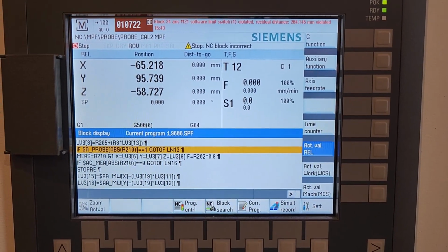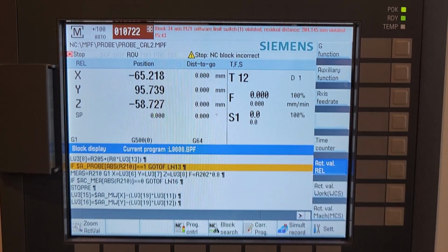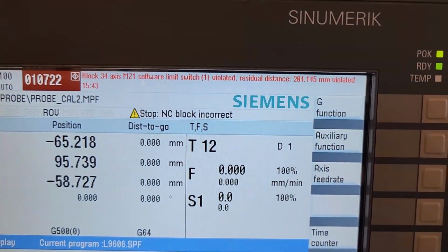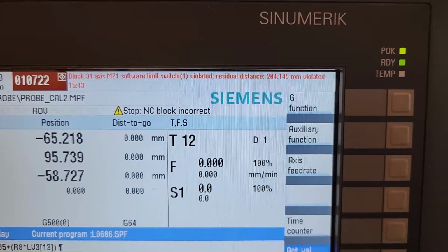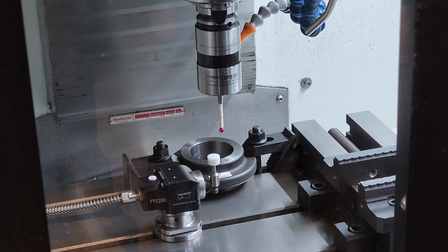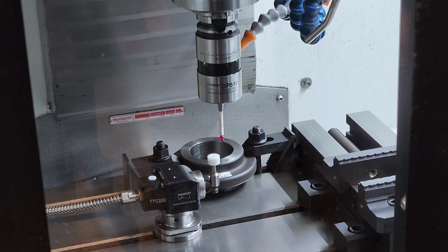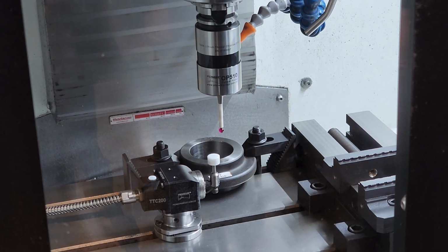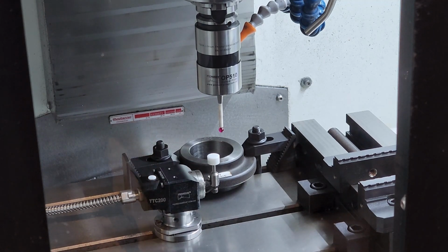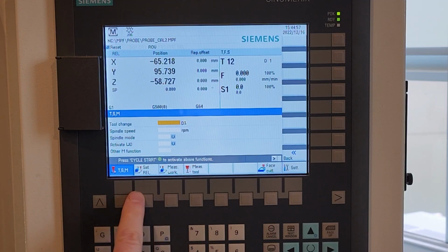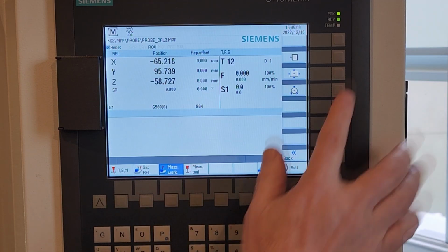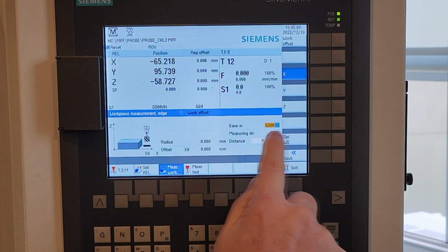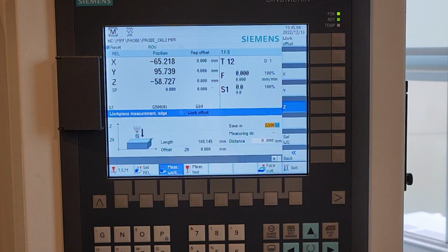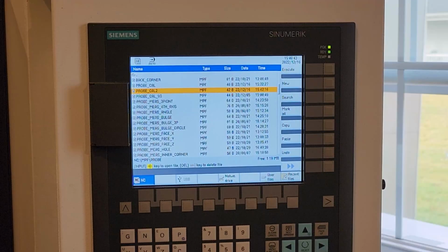This is probably a user error on my part. Perhaps I'm missing some crucial information to understand how to run this calibration. I have found a couple of hacks to calibrate the length of the probe, although I don't think they are as accurate as a third technique that I'll go over last. One way to get the routine to run and not get an error is to set G500 in Z to 0, and then change the R3 variable in the program to -10.